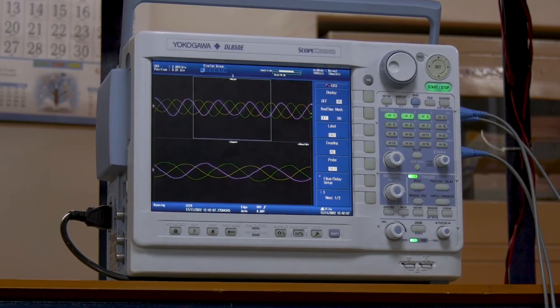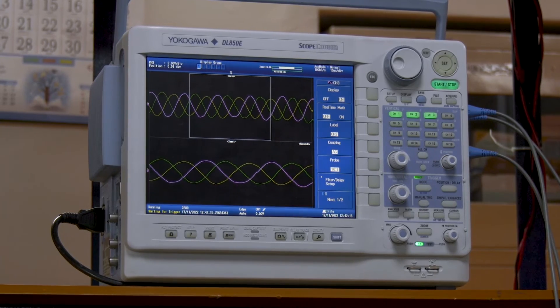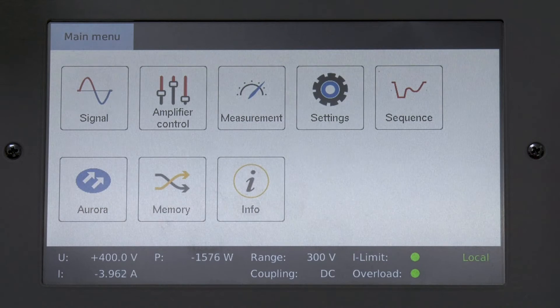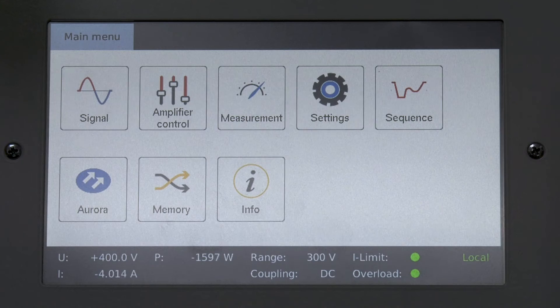Moving to the second test case: similar to the previous case, the power generated by PV and BESS is less than the DC load connected at the DC bus. By looking at the DSO, we can observe that the increase in DC load reflects the current magnitude. Looking at the power amplifier power sign — which is negative — means power is flowing from the AC grid to the DC bus. So earlier it was DC to AC grid, and now it is AC grid to DC bus. The DC bus voltage is always regulated to 400 V. From these test cases we have witnessed the energy exchange between the AC grid and DC microgrid.